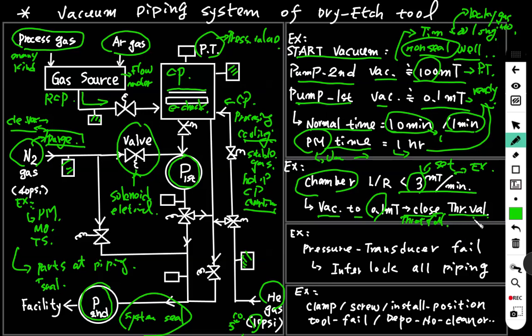And you can see the PT pressure transducer value for 1 minute. If it increases above 3 in 1 minute, it means a leak condition you cannot accept. You have to do troubleshooting. That's the simple calculation to verify the leak situation.